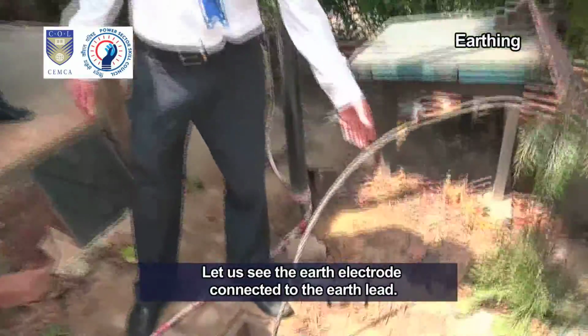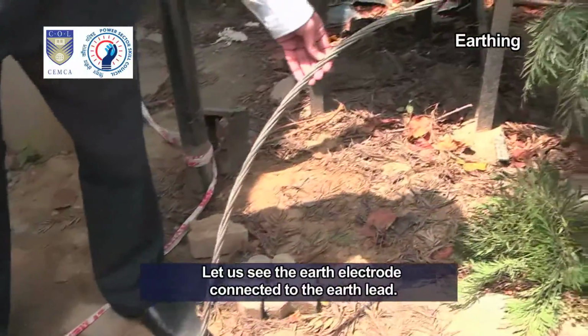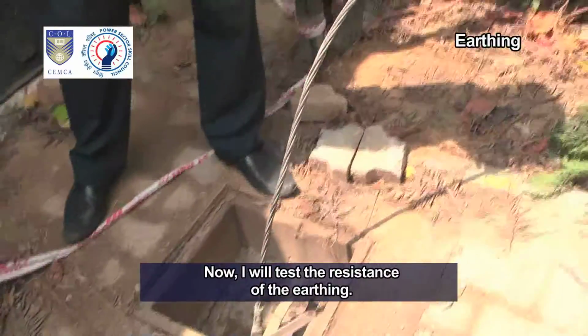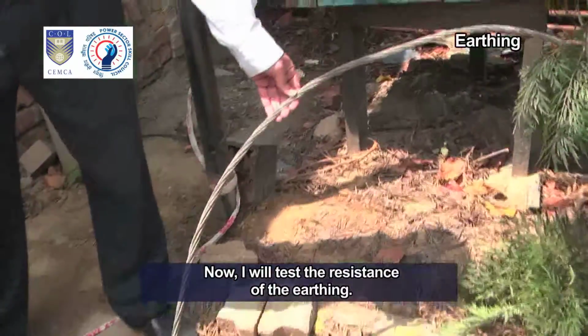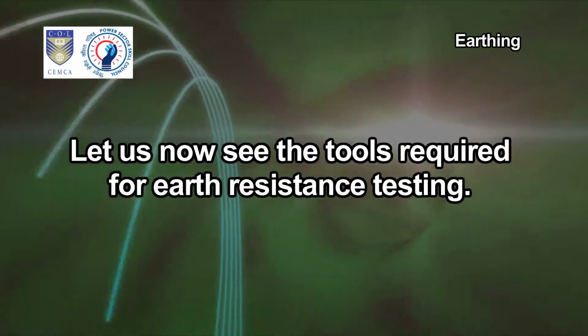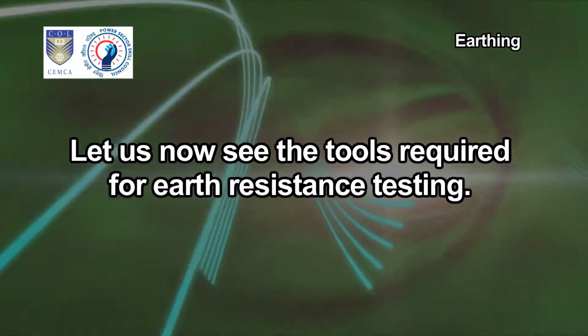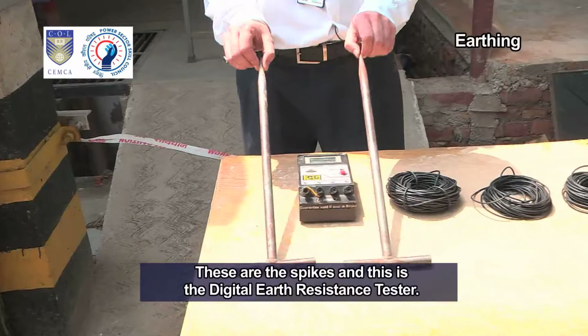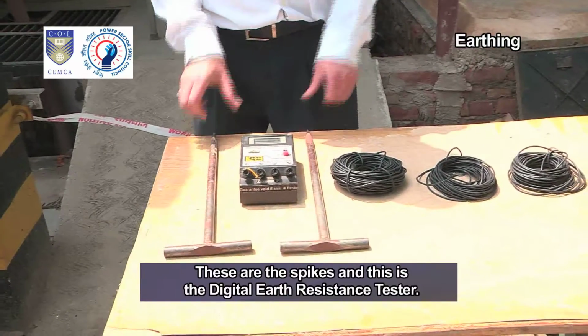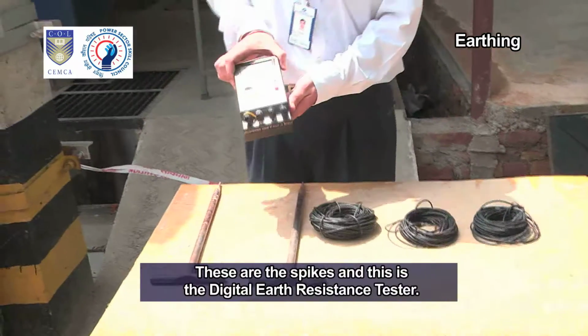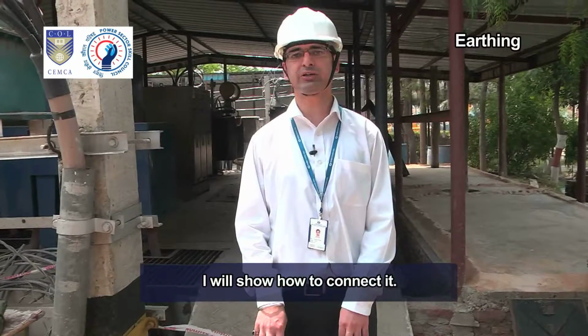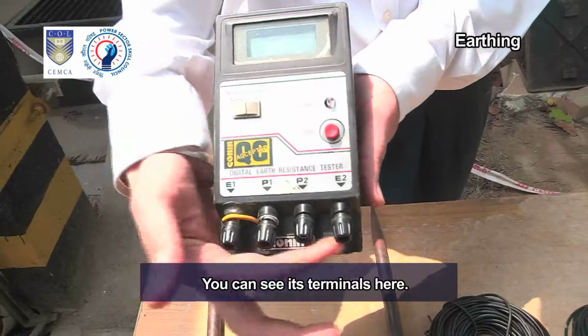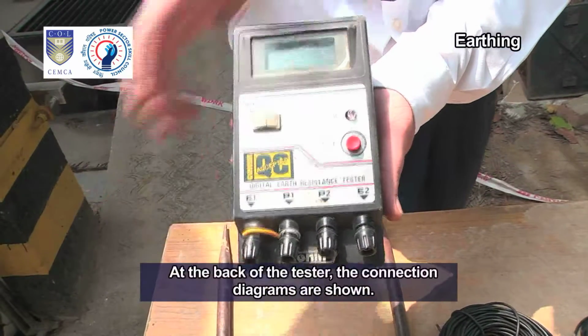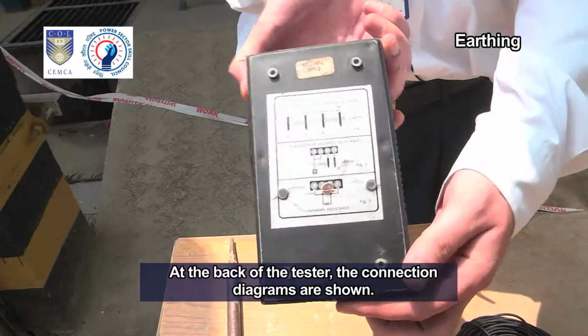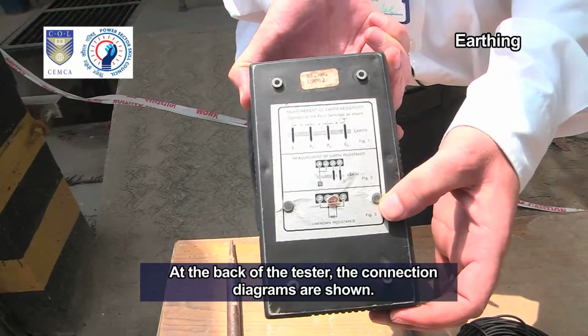Let us see the earth electrode connected to earth lead. Now I will test the resistance of the earthing. Let us now see the tools required for earth resistance testing. These are the spikes and this is the digital earth resistance tester. I will show how to connect it. You can see its terminals here. At the back of the tester, the connection diagrams are shown.